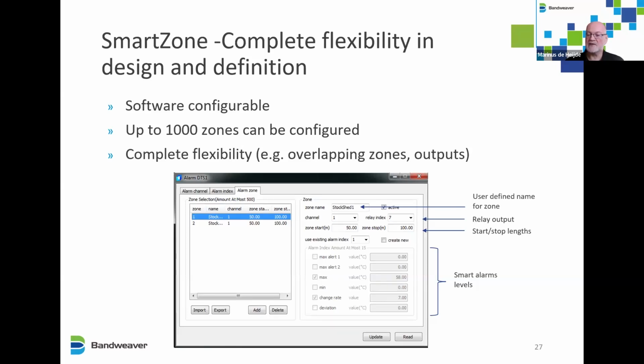And we can then also set different smart alarms at these zones. So we can have a maximum alarm number 1, but we can also set a maximum alarm number 2, for example if you want a pre-alarm at a lower level. So if you have a maximum alarm at 60 degrees, you can set a pre-alarm at 50 degrees. You can then send somebody to have a look and see what's happening. It's not necessarily a fire. An alarm is not set off, but you can check what's happening. And the same with the rate of change and the deviation alarms.